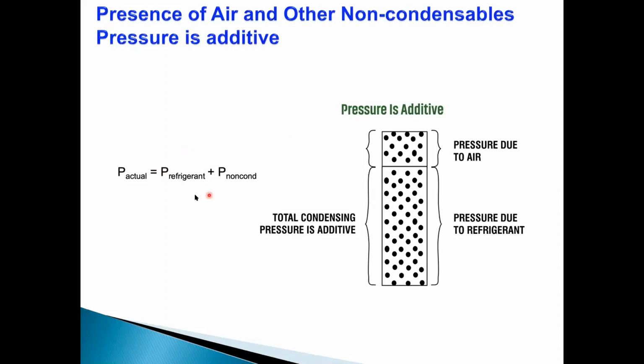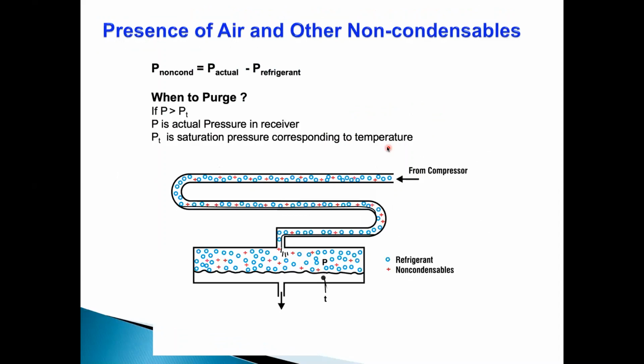We have refrigerant pressure, and if there are non-condensable gases or air in the plant, the actual pressure is higher. It means that theoretically at 35 degree condensing, our pressure should be 13.5. But if air is there and is 1 kg pressure, our actual pressure would be 14.5. So this is the excess pressure, which is the air pressure. And you can very easily check and measure whether your plant has air or not. It's very simple. For the liquid coming from your receiver, you know the pressure on your receiver.